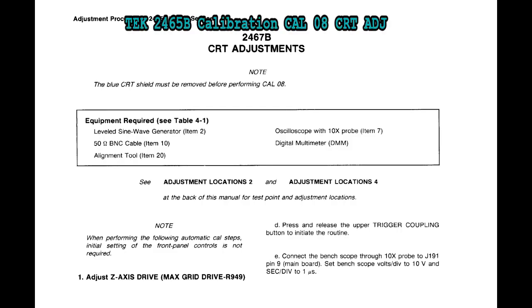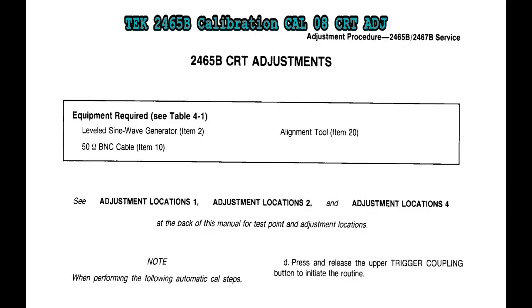The first Cal 8 you come to is not on page 5-7. It's actually on page 5-4. If you look at the top there, it says 2467 Bravo. You don't want to be there if you have a 65. You want to be on this page here, 5-7 again, where it actually says 2465 Bravo.